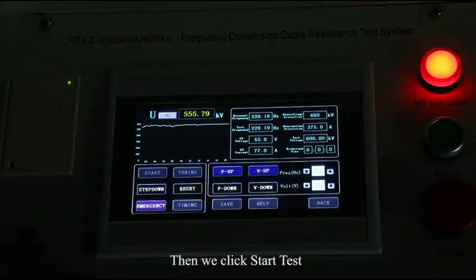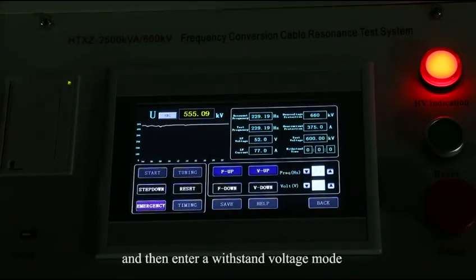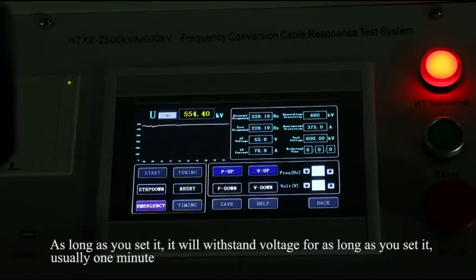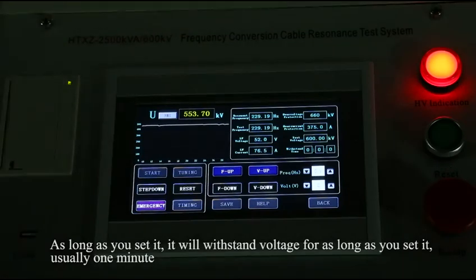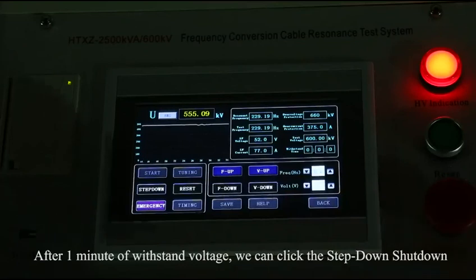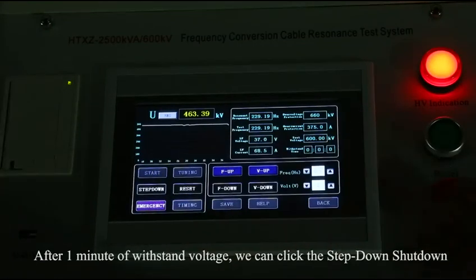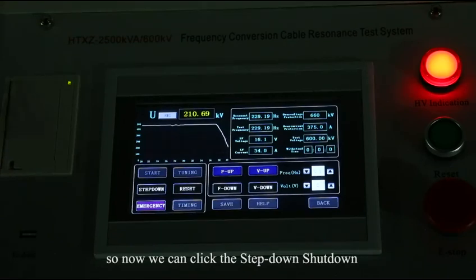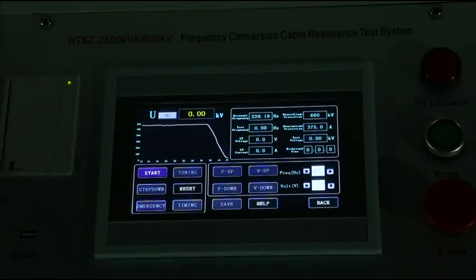Then we click Start Test, and then enter a withstand voltage mode. As long as you set it, it will withstand voltage for as long as you set it, usually 1 minute. After 1 minute of withstand voltage, we can click the Step Down Shutdown. So now we can click the Step Down Shutdown.